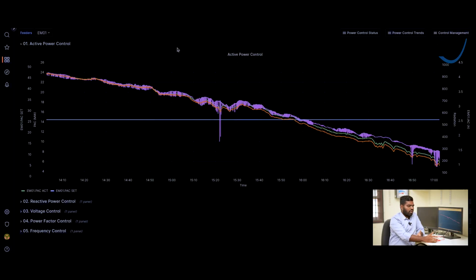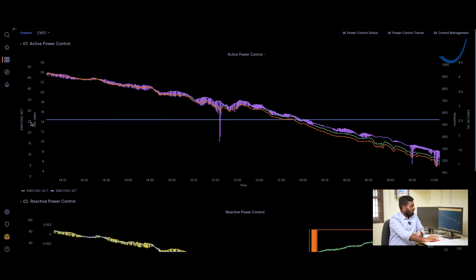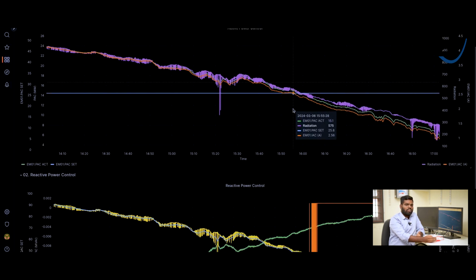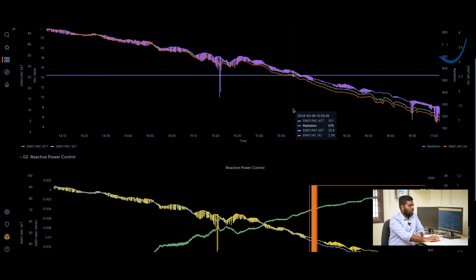And another trend screen is feeder wise trends. In this 50 megawatt plant, two feeders are there, and each feeder has 25 megawatt. Here we can check energy meter 1 on feeder 1 and energy meter 2 on feeder 2. Here we can check active power control and reactive power control. On the left axis we can check active power and the active power set point limit. On the right axis we can check radiation and current. We can also compare these two feeders.